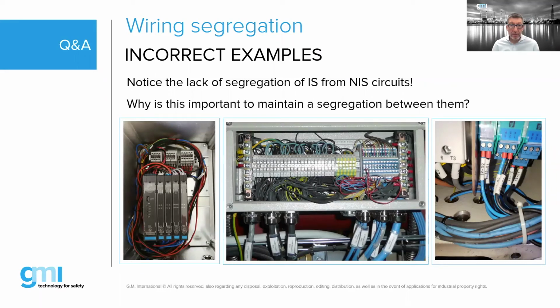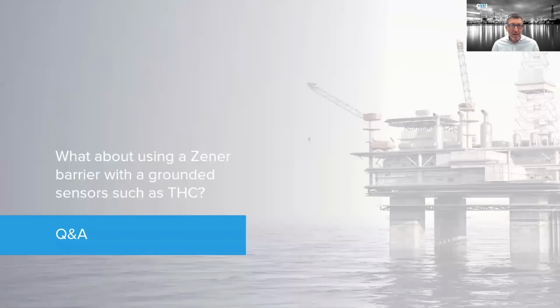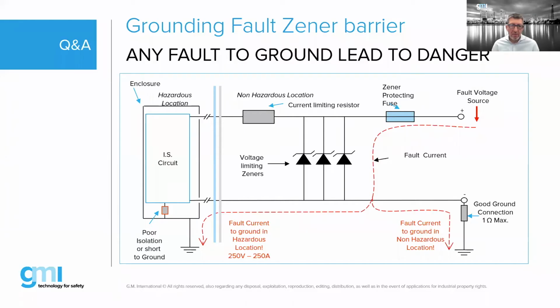Okay, good. Well, I keep looking at the questions coming in, guys, and we are almost into an hour. Well, there was a question about Zener barrier with a grounded sensor. You discussed this earlier, Bob. You cannot use a grounded sensor because you create two paths for the fault current to ground. So isolation in the field is required, minimum 500 volt, right? Correct. We have a live question here that you might want to look at, Bob, while I go forward, because it sounds complicated.